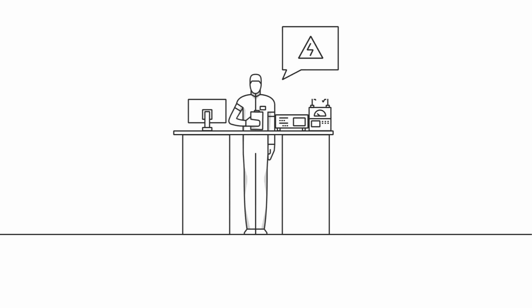If a fault occurs inside switchgear, it is essential that the protection decision is selective. This means that only the part of the switchgear affected by the fault should be isolated as quickly as possible. To do this, Matthew must integrate his protection scheme in the protection relay with selective protection, that is, zone-selective tripping. He also wants to include active arc flash protection with the relays, and he is using both light and current conditions in his scheme. Next, Matthew has to consider how to design the protection scheme if arc flashes happen in different parts of the switchgear.